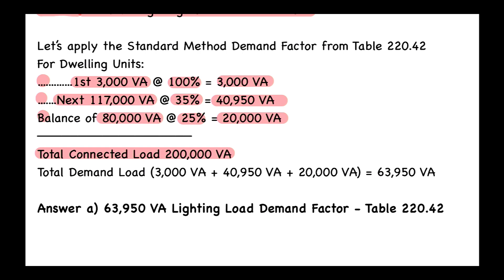It's really important to start with the connected load and apply the first 3,000 VA, then up to 117,000 VA at 35%, and if anything remains, take the balance at 25%. Adding up: 3,000 VA + 40,950 VA + 20,000 VA equals 63,950 VA total demand load. The answer is A — 63,950 VA for the lighting load demand factor from Table 220.42.